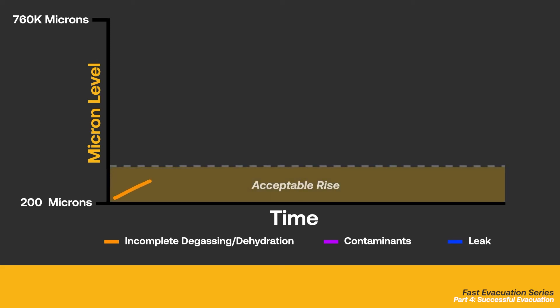If the system maintains a slow rise and eventually levels off at a relatively low micron level, this means that the system was not fully evacuated and is still equalizing. This will require continued evacuation.